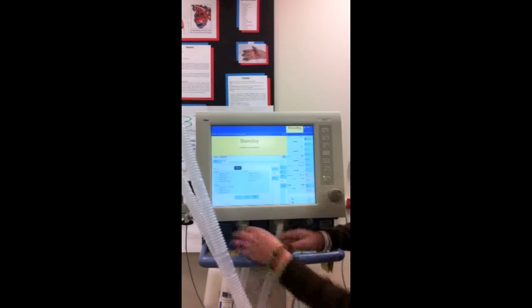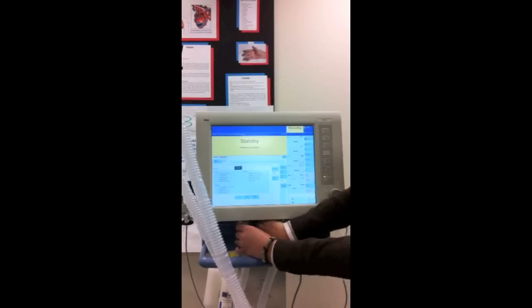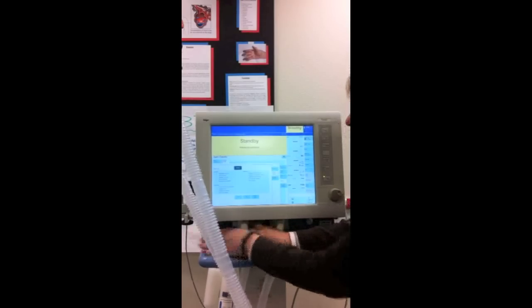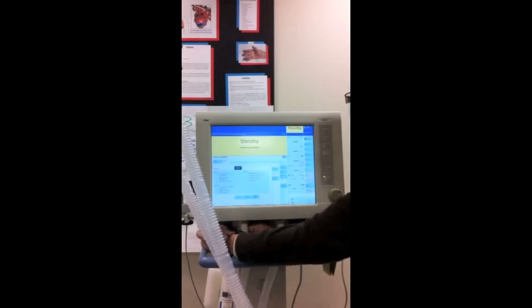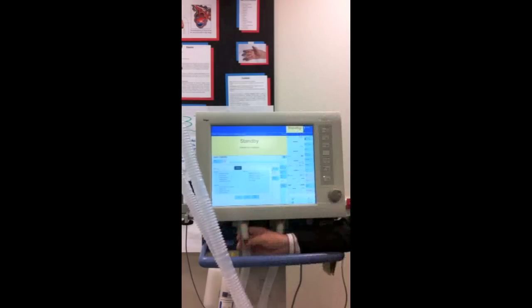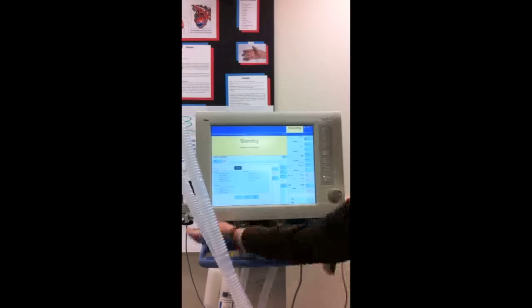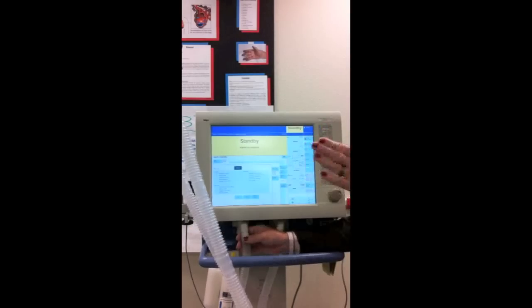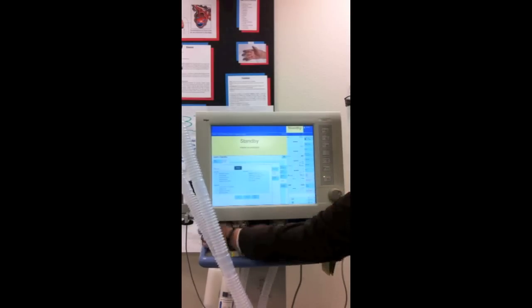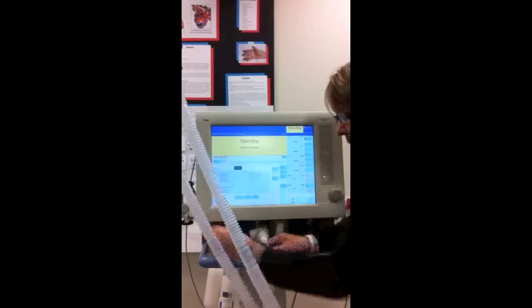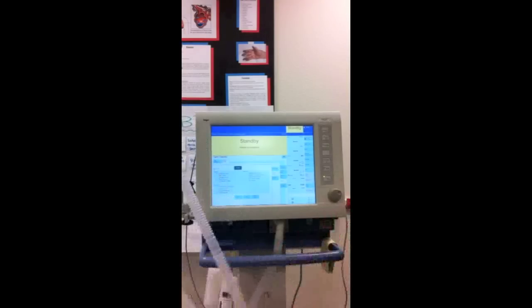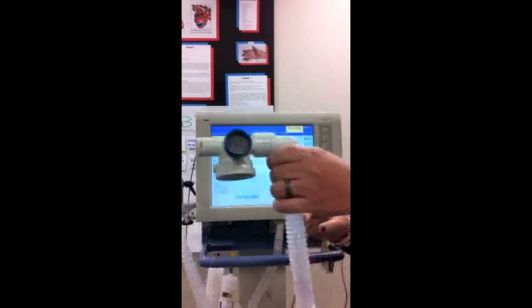This has the wrong knob. It has a little blue tab here you have to push in to pull it out, and on this flap is the flow sensor. If you pull this out without moving the flow sensor, it will fly across the room and can break. So it's important because the flow sensor actually pushes into the side of the exhalation valve. So it's important to just pull it out slightly by pulling it to the left, and then you can pull your exhalation valve out. This is the exhalation valve on the Dräger.